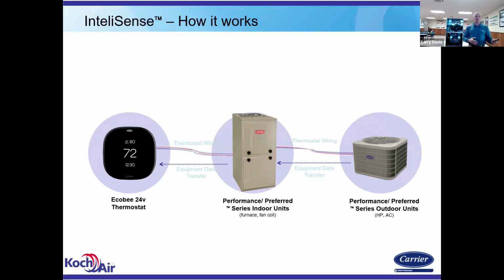It sends that information back to the portal. And that's the portal that you log into. So you can access that information and pull it up and look at how that system's operating before you go to the service call. You cannot pull that information up, and the homeowner cannot pull that information up at the thermostat. It's only accessible through the portal. IntelliSense is really designed to be a service tool for you to kind of give you an edge on what's going on with that system before you get out there. Or if maybe you have a service manager that's back at the office, they can screen that information and make some preliminary diagnostics before the technician rolls out to the job site. So that's what the IntelliSense is all about.